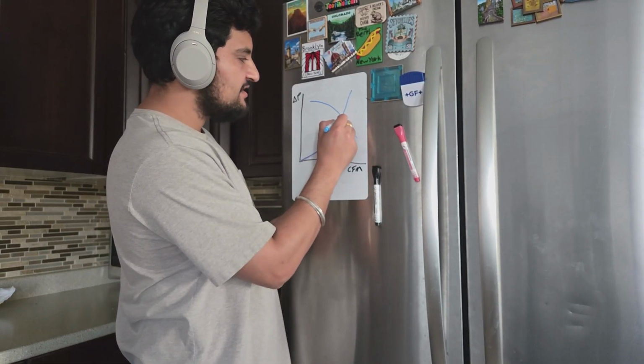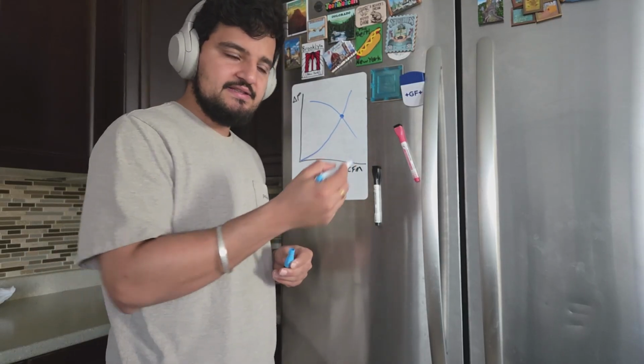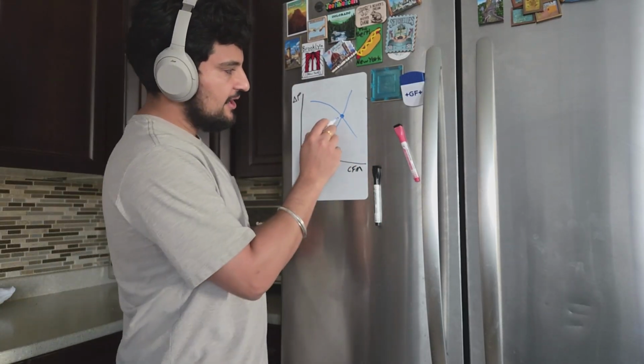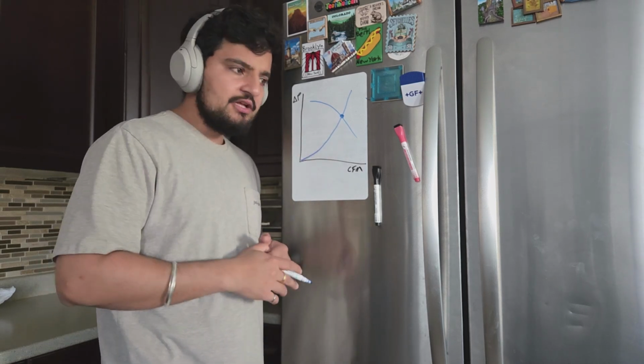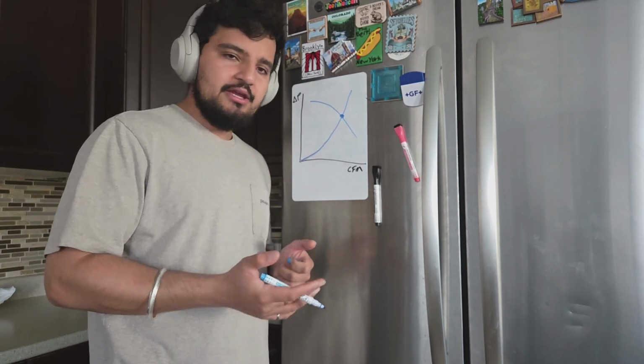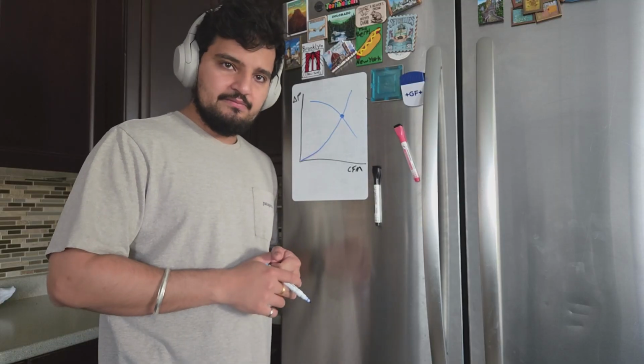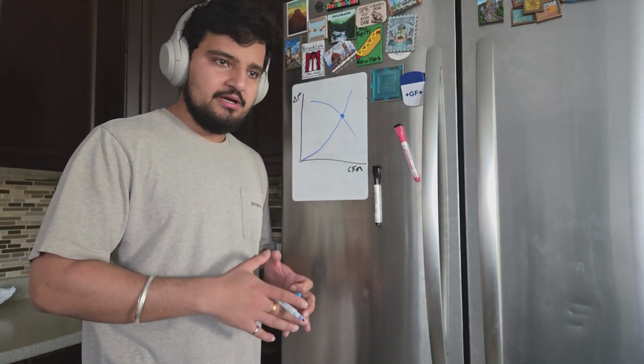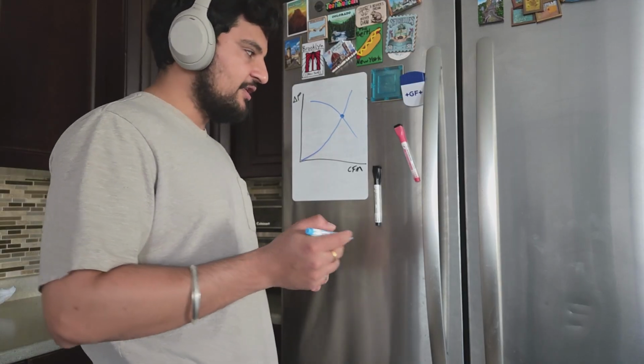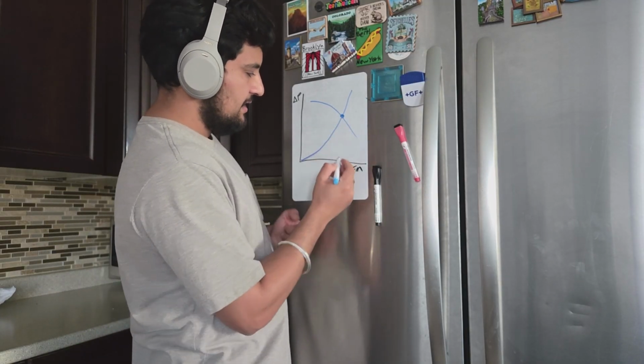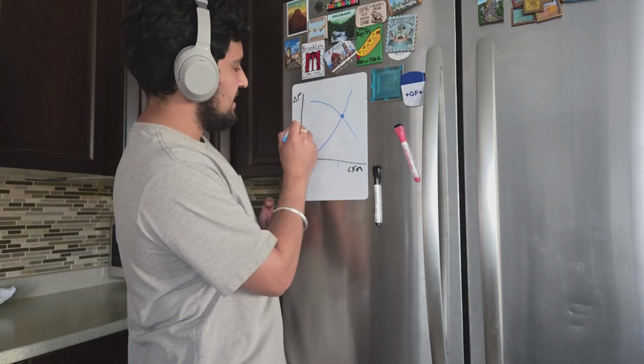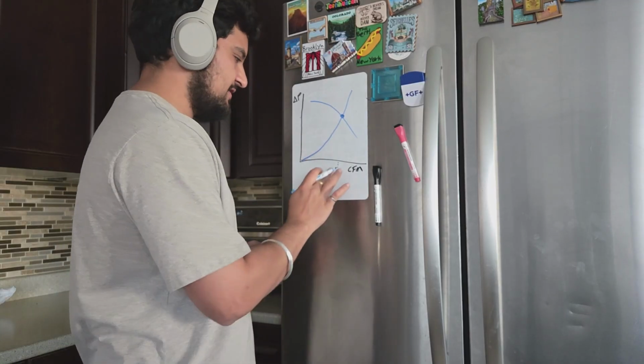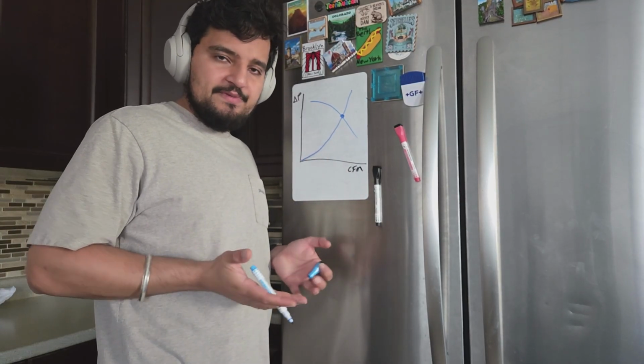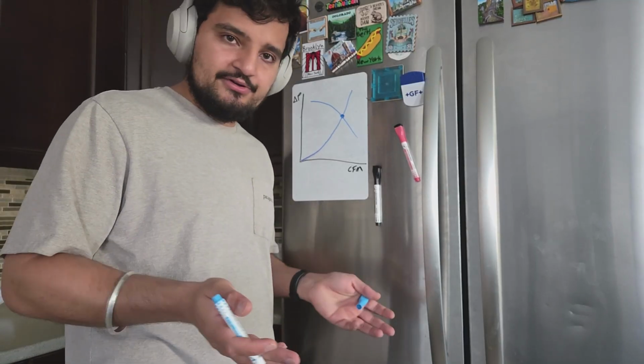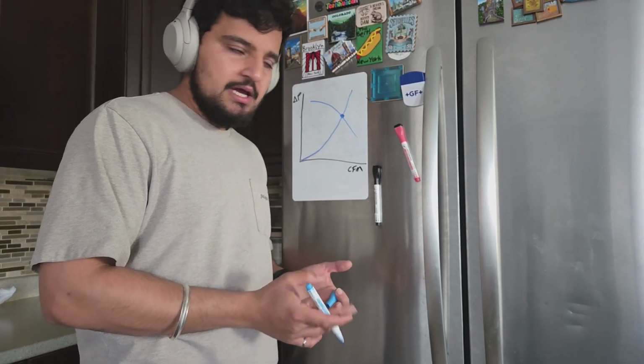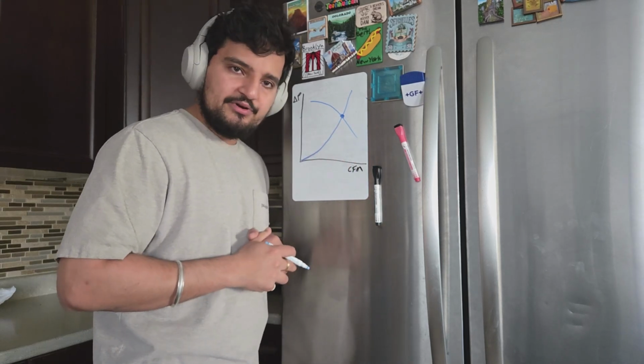Now, the point at which these two curves intersect is called the operating point. This is where your fan is operating, right? So let's say the manufacturer says that your air handling unit is able to deliver 1,000 CFM at 0.3 inches water column, right? So what they're basically saying is this operating point, 1,000 CFM at 0.3 inches water column pressure loss. In reality, your pressure loss through your ductwork might be something else because you've changed the dampers, maybe your filter's dirty, maybe the designer didn't consider something. So now your operating point is here.